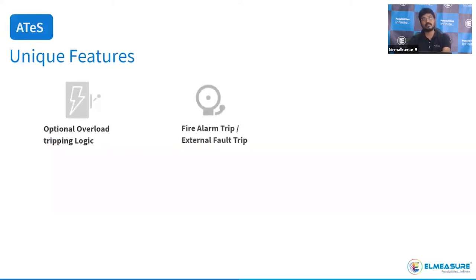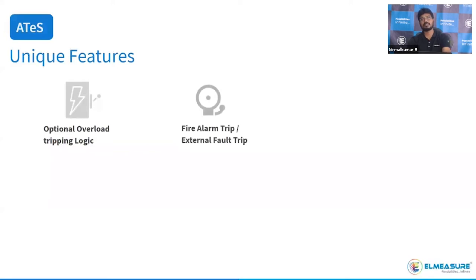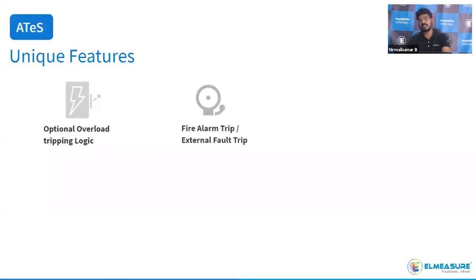Fire alarm trip and external fault trip are also available. Our ATS can be integrated with a firefighting generator — a mandatory requirement in every commercial mall, hospital, and shopping mall. In case of a fire alarm input, our ATS will not only initiate the backup generator but also the firefighting generator. So we can control two generators: one backup generator and one firefighting generator.